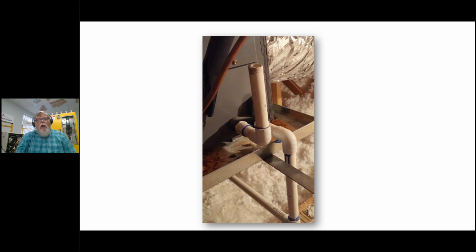Now, as far as the line on the right, the primary, I don't know if there's a trap down there. It doesn't look like it. And if there's no trap, it's doing the same thing. It's holding the water in until the unit cuts off, and then the water can flow through the pipe. But you can tell there's rust in that pan. So every now and then it fills the condensate tray completely up, it runs over, and it drips into the emergency pan. In an ideal situation, you would never have any water in the emergency pan unless it was an emergency. Something really fouled up on the system.